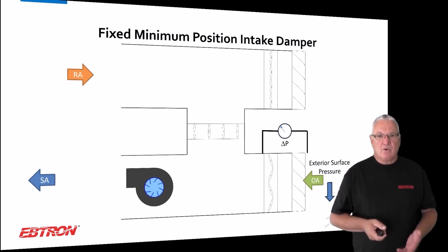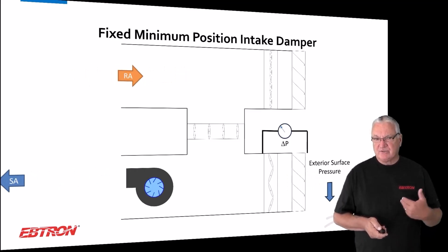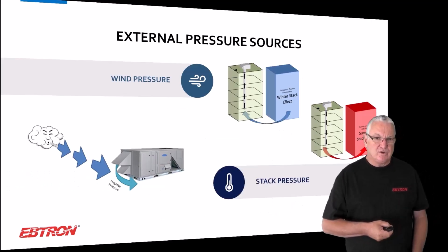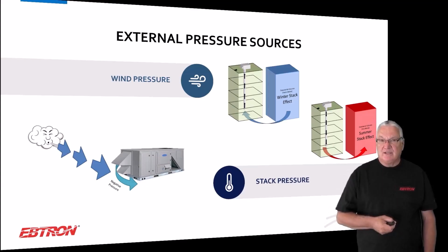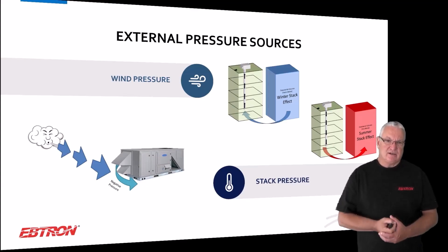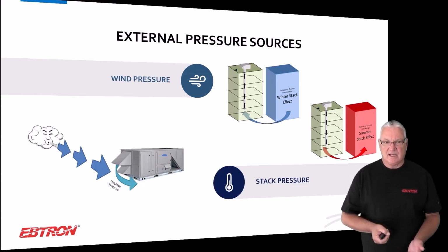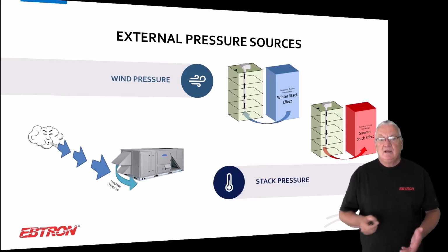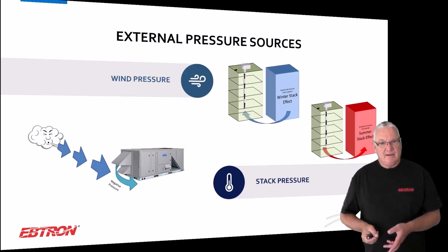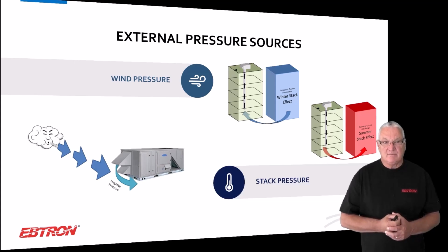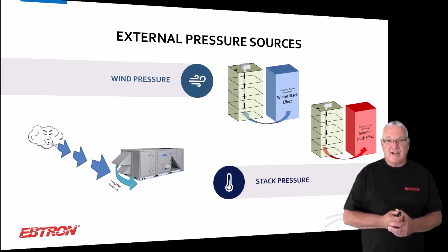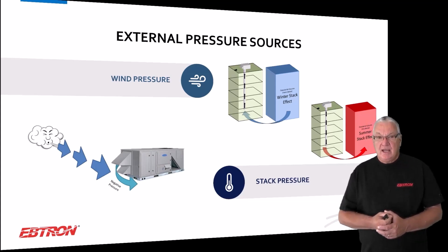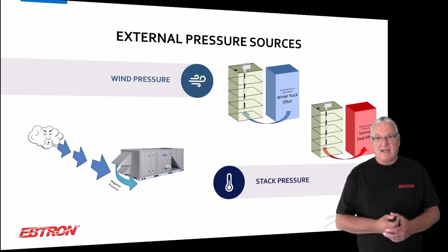All right. So we want to look at what exterior surface problems we could have, and what are those particular sources. Well, it's wind for one thing, and even though what I'm showing you here is an illustration of a rooftop unit, it doesn't matter if it's ducted or not ducted. You have pressure changes from wind. You may protect those intakes a bit on the roof, but to be honest with you, they're going to be affected by wind pressure changes, and stack pressure changes. You're not going to protect that at all.